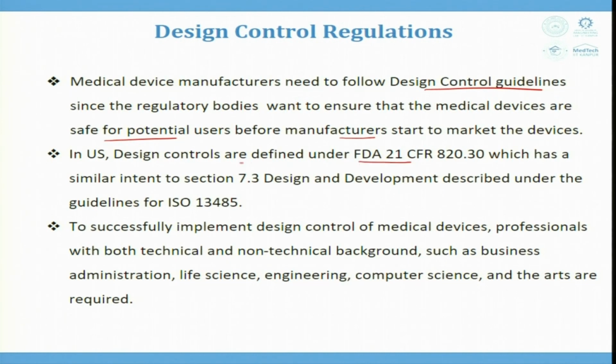In the US, design controls are defined under FDA 21 CFR 820.30, which has a similar intent to section 7.3, that is design and development, described under the guidelines of ISO 13485. To successfully implement design control of medical devices, professionals with both technical and non-technical backgrounds such as business, administration, life science, engineering, computer science and arts are all required.